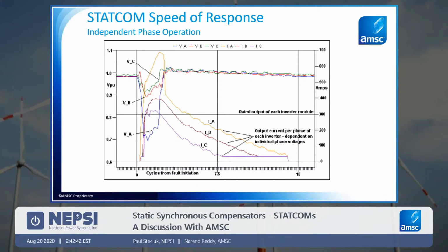And then, if you look at it, the dvar system, as soon as it detected that, injected currents on different phases with respect to how that sag was recorded, and it responded fast and brought the voltages back up. But as soon as the sag event went away, as soon as the voltages came back to nominal, you will see that the system ramped down very, very quickly.